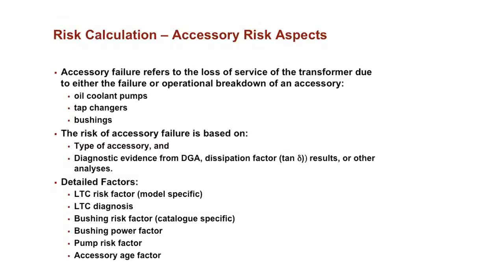Then there's accessory risk. Again, a bushing or a tap changer can fail a transformer. It's unfortunate when an accessory such as a bushing or tap changer fails a transformer, because you can do maintenance on these accessories and look at them to see how they are. For example, if a bushing fails, perhaps it explodes, and then it can put porcelain through the transformer and maybe not even fail the transformer, but it contaminates it. In a lot of cases, it requires the transformer to be rewound, just because you don't know where all that contamination went. And that's for a component that is maybe only $10,000. So it's very important to be looking at the condition of bushings and tap changers.